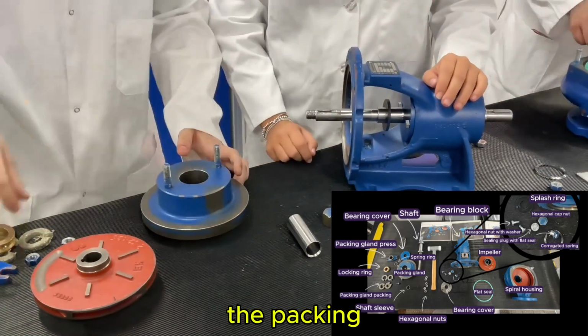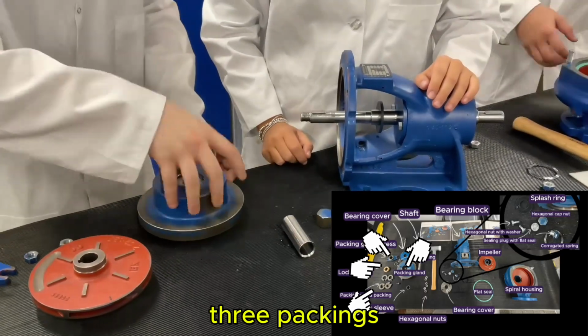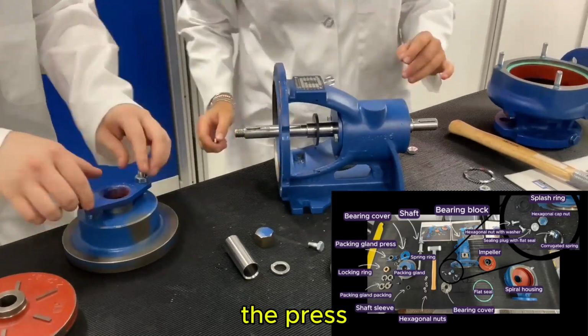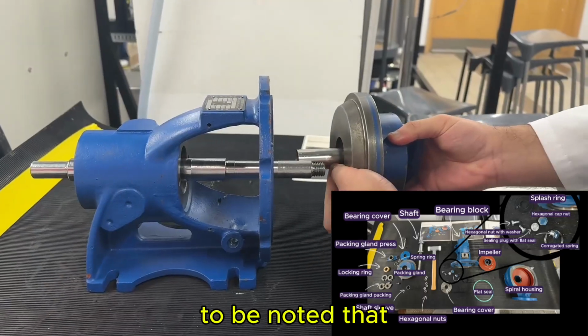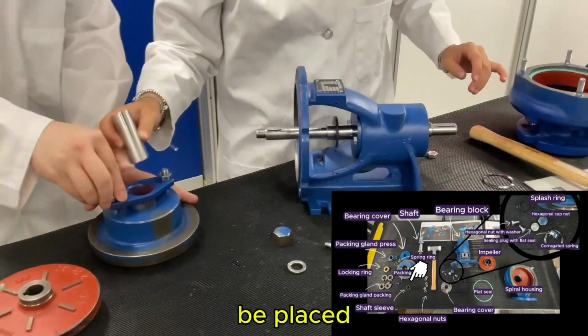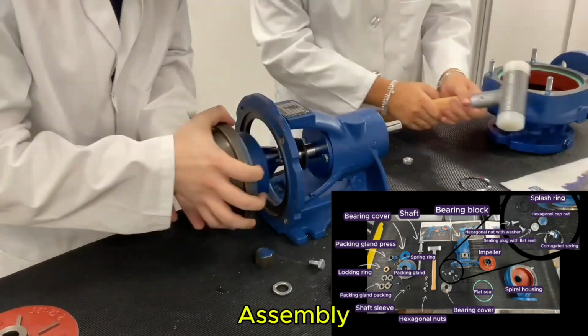We then assemble the packing gland by placing a packing, then the locking ring followed by 3 packings into the housing cover, then securing the press on top of it using hexagonal nuts with washers. It is to be noted that due to technical issues, the shaft sleeve could not be placed on the shaft. This does not disregard the general assembly procedure.